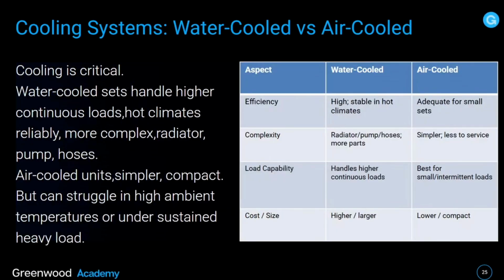Cooling: water-cooled versus air-cooled. Straight off the bat, a water-cooled system is a more robust system than air-cooled, and they're generally a quieter genset. Cooling is critical. Water-cooled sets handle higher continuous loads and hot climates. They're more reliable, but they do have more complex radiator, pump, and hose setups. Air-cooled units are simpler and compact, but can struggle in high ambient temperature under sustained heavy load. And that's because they're air-cooled.